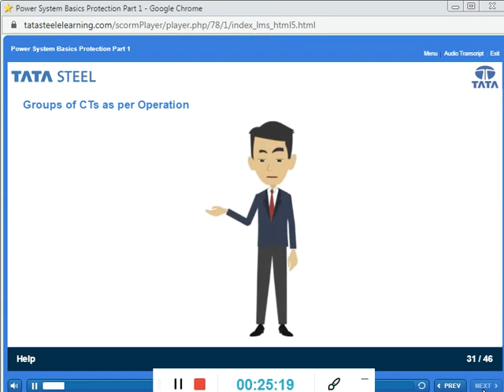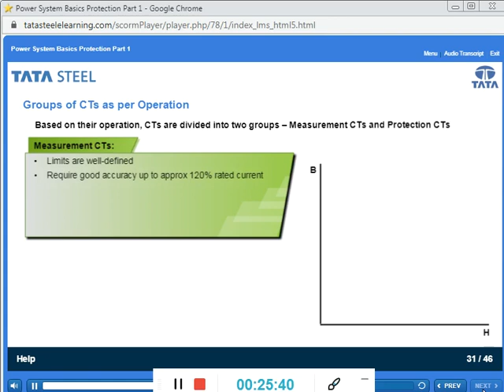We have learnt about groups of CTs as per construction. Similarly, based on their operation, CTs are divided into two groups: measurement CTs and protection CTs. Both have different characteristics. Let's look at them in detail. Measuring CTs: limits are well defined. They require good accuracy up to approximately 120% rated current. They require a low saturation level to protect instruments. Thus, they use a nickel iron alloy core with low exciting current and knee point at low flux density. Measuring CT is more accurate than protection CT.